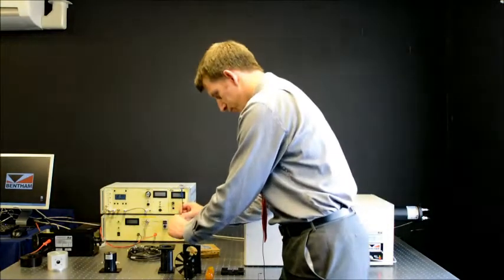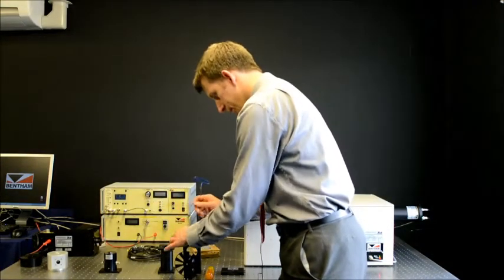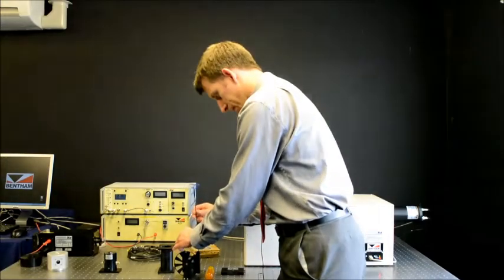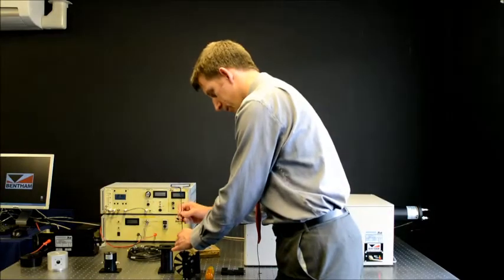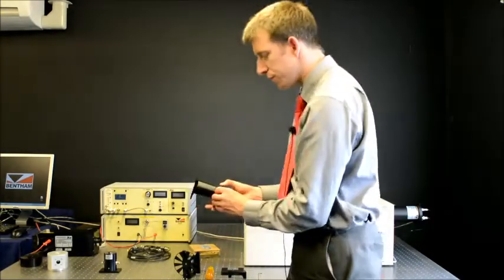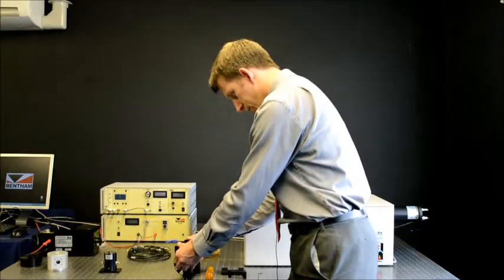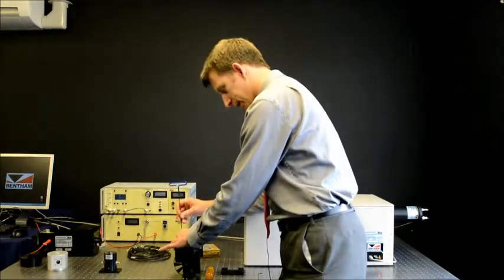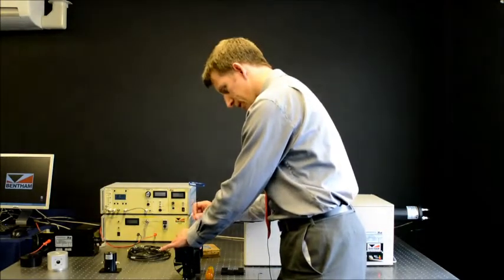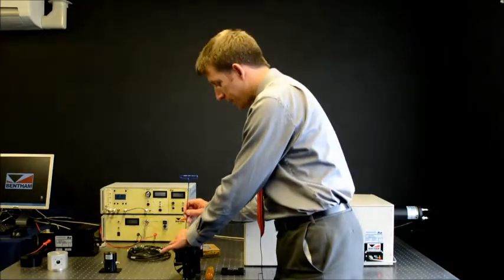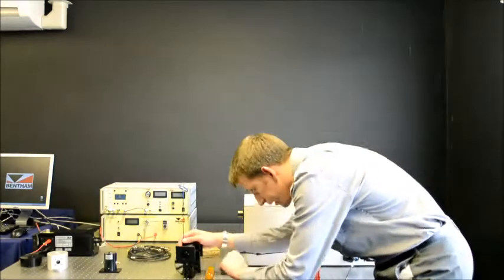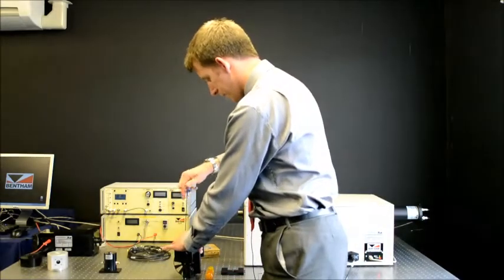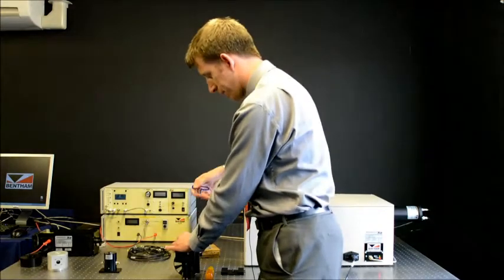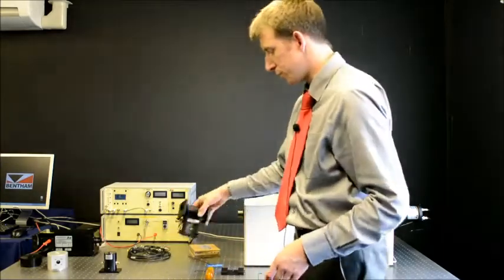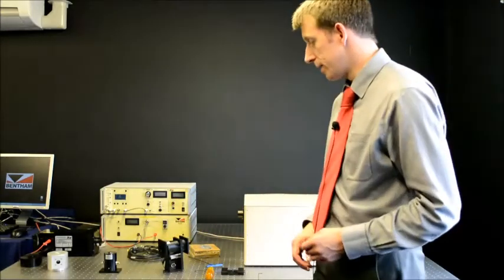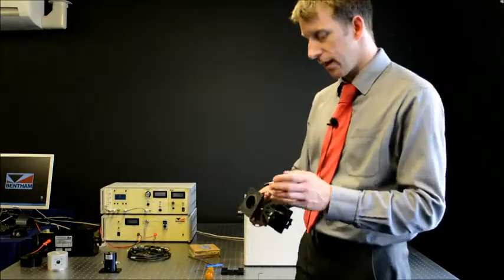We then remove the clamp of this assembly and then place thereupon the relay optic. The groove of the relay optic fits over the chopper blade, and one can place the clamp in place, attach it more or less, not entirely, before ensuring that the blade moves freely, adjusting position as required, and then finally tightening the clamp up. Once you have done this, you can simply keep this relay optic in this way, paying attention not to hit the blade, else it will be bent.